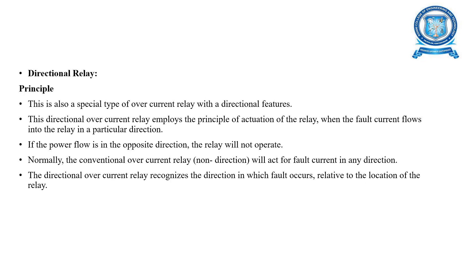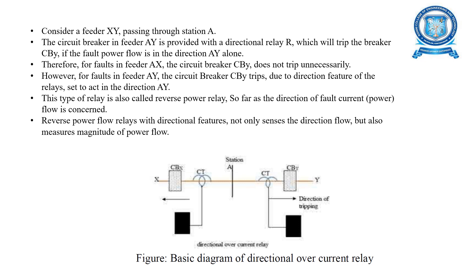Next is the directional relay. The main principle is that the directional overcurrent relay actuates when fault current flows into the relay in a particular direction. If power flows in the opposite direction, the relay will not operate. The directional overcurrent relay recognizes the direction in which the fault occurs relative to the relay's location. Here is the basic diagram of a directional overcurrent relay considering feeder XY passing through station A, with circuit breaker CBY provided with directional relay R.